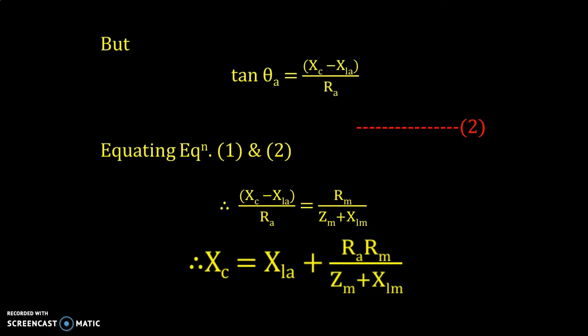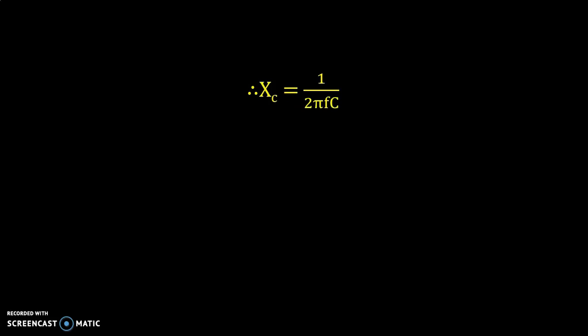With this equation we will be able to find the value of XC, which is the reactance of the capacitor. Once we have the value of XC, we know that XC = 1/(2πfC), where C is the capacitance. Therefore, capacitance C = 1/(2πf × XC). With this, we can calculate the value of capacitor to generate maximum starting torque. Thank you for watching my video, keep watching, thank you very much.